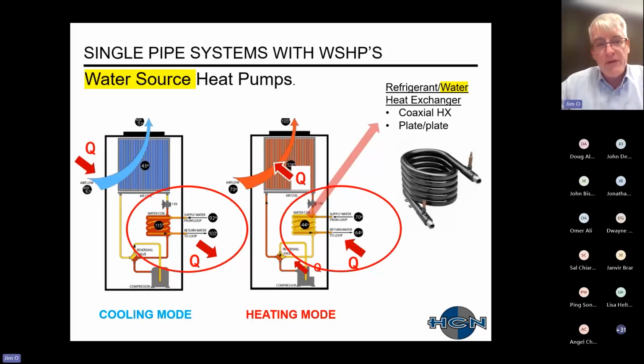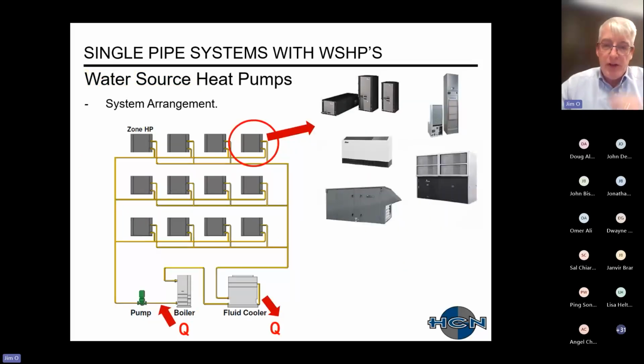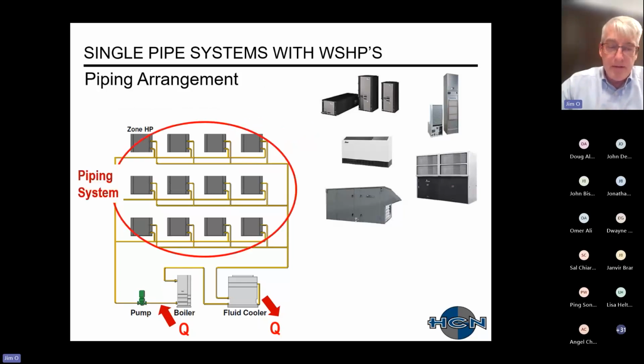With water source heat pumps, you have a coaxial heat exchanger, which could also be a plate and frame heat exchanger. This is obviously used in cooling mode as well as heating mode. With the water source heat pump, here's a typical arrangement. You have multiple types of water source heat pumps. The picture up on the right gives a plethora of different units. You end up with a piping system feeding those water source heat pumps. And then, similar to a chiller boiler system, you have utilities or devices that are providing heating as well as heat rejection, etc.